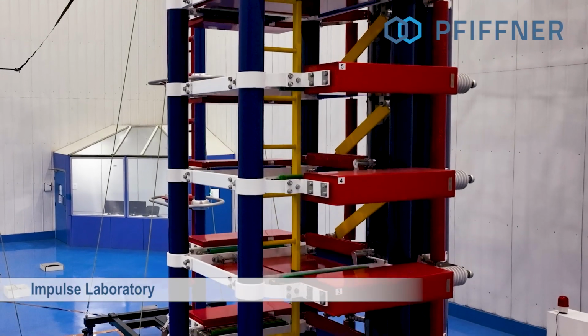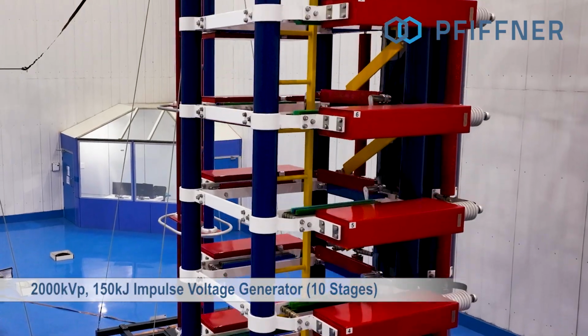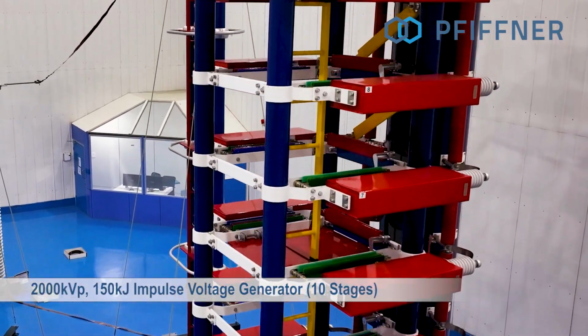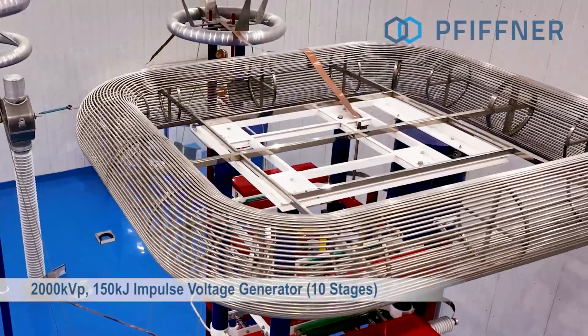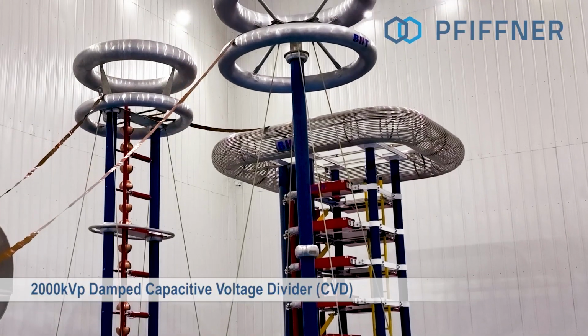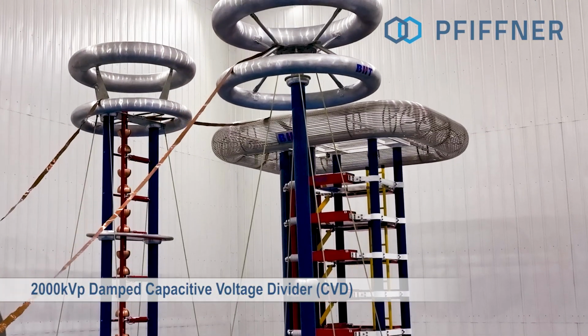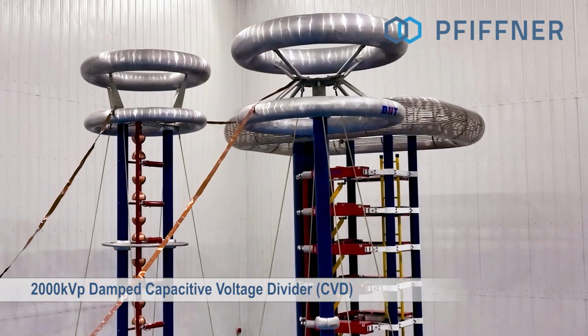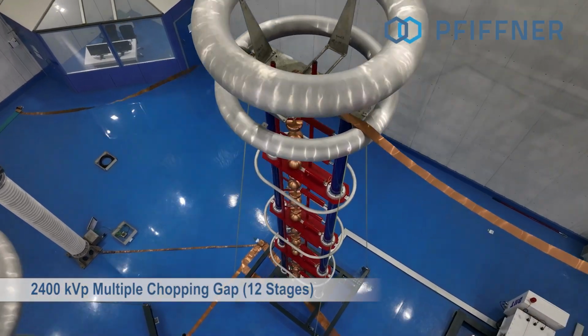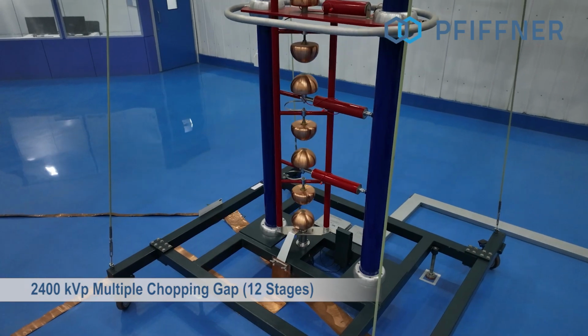Impulse laboratory is equipped with 2000 kVp, 150 kilojoule impulse voltage generator, 10 stages, 2000 kVp damped capacitive voltage divider, CVD, 2400 kVp multiple chopping gap, 12 stages.